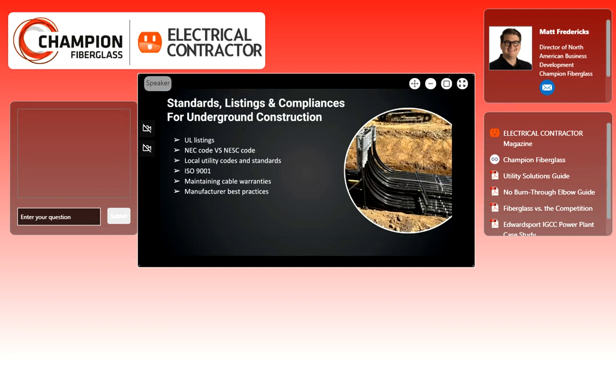A couple other things that I will mention too. When you're doing underground construction, it's certainly important to read those UL listings and the NEC code. Also, if you're a utility, pay attention to the NESC code. Those three things will really guide you on what's able to be used and what's not able to be used in many different situations for underground construction. Additionally, local utility codes, as well as building standards, will guide you as well. There might be specific conditions in the area that you're doing construction in where specific soil types are present. So a utility or the building codes may require that metallic sweeps be wrapped in non-corrosive tape. Just the nuances of doing construction everywhere. So it's important to pay attention to those, make sure that you're in compliance.